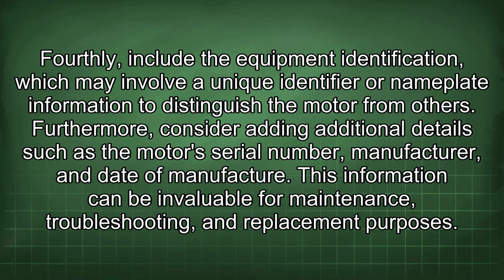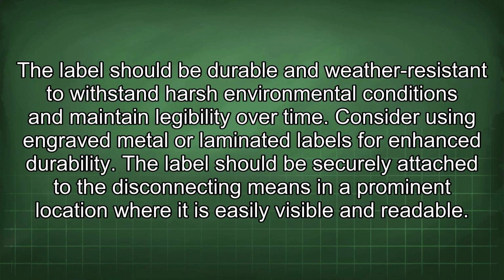Furthermore, consider adding additional details such as the motor's serial number, manufacturer, and date of manufacture. This information can be invaluable for maintenance, troubleshooting, and replacement purposes. The label should be durable and weather-resistant to withstand harsh environmental conditions and maintain legibility over time. Consider using engraved metal or laminated labels for enhanced durability.